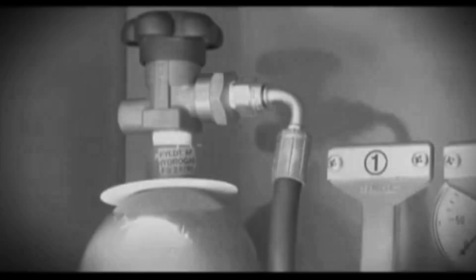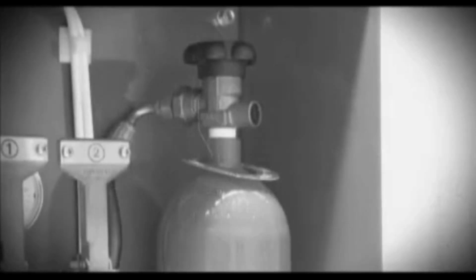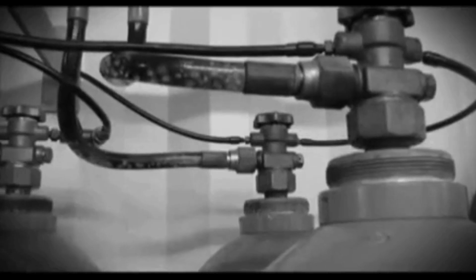In the stress of the situation, the officer ordered to operate it forgot the instructions. He believed he was looking at an operating system with a backup, and he only operated the first lever. Hours later, he realized he had not operated the system correctly. He decided to check the carbon dioxide room. It was obvious that no carbon dioxide had actually reached the engine room. By then, the fire had burnt itself out, completely destroying the engine room.